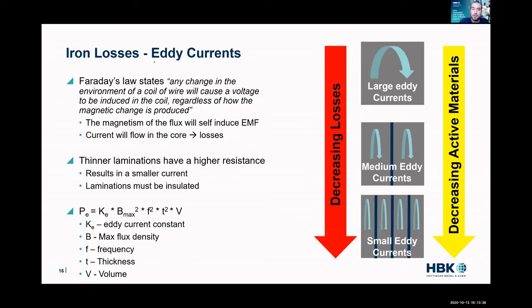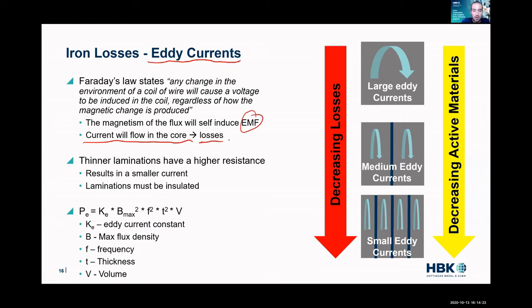The next factor we have is iron losses, and in those iron losses we have eddy currents. Faraday's law states that any change in the environment of a coil of wire will cause a voltage to be induced in the coil, regardless of how the magnetic change is produced. So if we turn a chunk of iron into a magnet, we're passing flux through it. Since iron is a conductor, it's going to have a self-induced voltage, and because iron has a resistance — V equals IR — we're going to create a current. Current will flow in the core because of that induced EMF, and we're going to create losses.